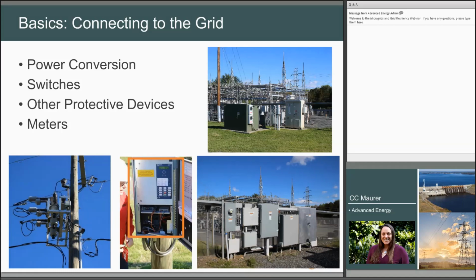A specific application for microgrids is called an islanding switch, which is used to disconnect the microgrid from the main grid. The islanding switch may be triggered by a weather-related event or other grid issue, but it also could be an intentional disconnect from the customer or utility for load shedding. Another protection device shown here is the disconnect switch for the battery system. All parts of the microgrid may need to be maintained in isolation from one another, and these disconnects are an important safety feature. Lastly, meters are important to collect information about the overall power output or input at various points in the system. These are used to measure generation, auxiliary power, and customer load. Meters also provide feedback on voltage and power quality. All of the above parts contribute to the overall cost of the microgrid.